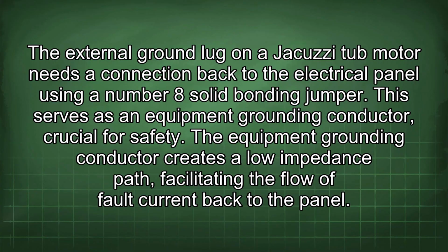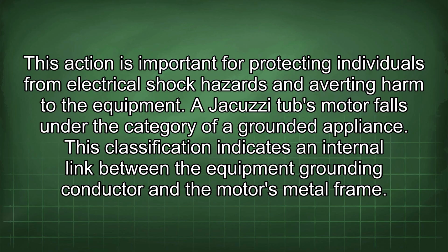The external ground lug on a Jacuzzi tub motor needs a connection back to the electrical panel using a number 8 solid bonding jumper. This serves as an equipment grounding conductor, crucial for safety. The equipment grounding conductor creates a low impedance path, facilitating the flow of fault current back to the panel. This action is important for protecting individuals from electrical shock hazards and averting harm to the equipment.